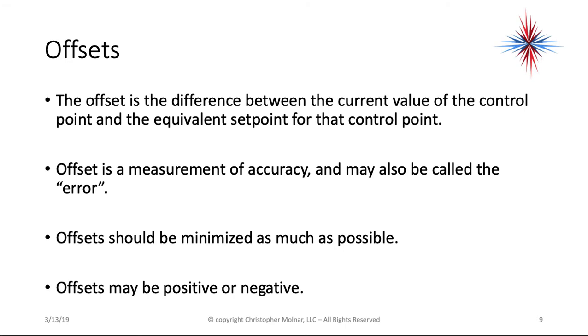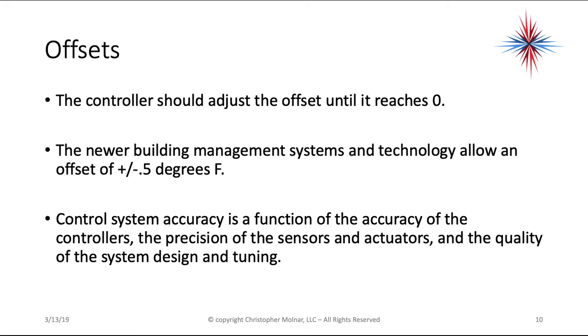Offsets are the difference between the current value of the control point and the equivalent set point — also referred to as the error. Offsets should be minimized as much as possible; they can be positive or negative, and the controller should adjust until the offset reaches zero. Newer building management systems allow an offset of plus or minus 0.5 degrees Fahrenheit. Control system accuracy is a function of the accuracy of controllers, precision of sensors and actuators, and the quality of building design and tuning.